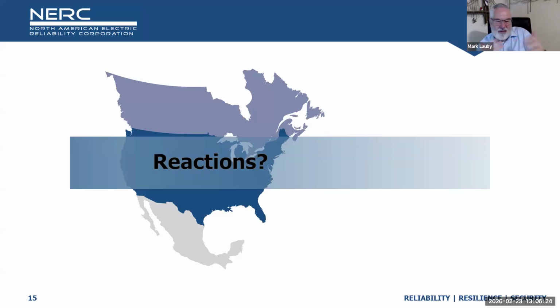But certainly we need that ability to provide frequency, which would also shore up and strengthen the system that we're weakening. They call it system strength, that short circuit stuff. So I see that being another component: damping, offsetting ramps, voltage support, frequency. Everything you used to get from a spinning machine, other than megawatts, we need to substitute for. I think inverters could do a lot of that. We might also want to think about synchronous condensers or other technologies too, if it makes sense. But anyway, that's a great question.